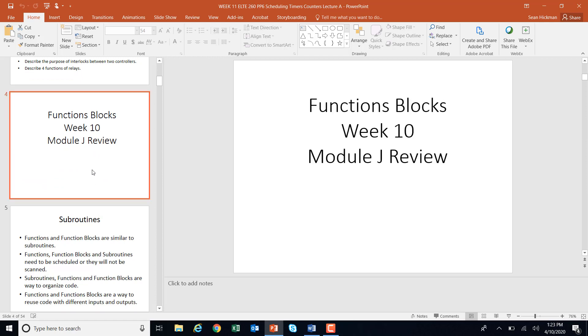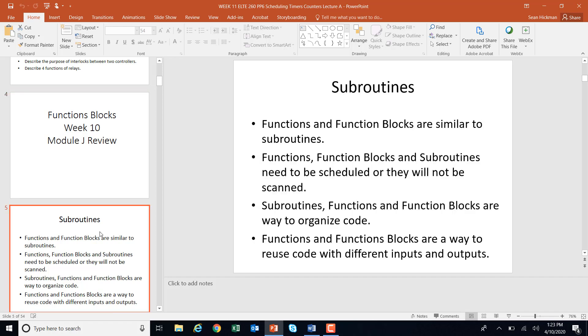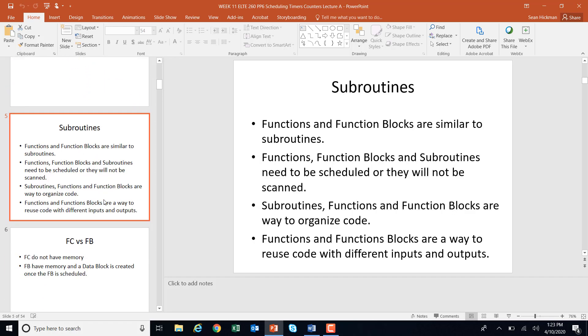Let's start with a review of function blocks from last week. Functions and function blocks are subroutines or similar to subroutines. They need to be scheduled or they will not be scanned. You have a main OB and you create these subroutines, then schedule them either conditionally or unconditionally into your main program. These subroutines are ways to organize and reuse code. For our lab, we were starting a motor forward and reverse, so instead of generating the function block code over and over again, we just scheduled it with different outputs — almost like copy and paste.